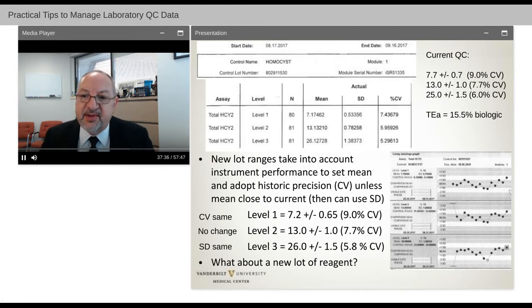the new ranges. So we set our level one, where the CV is the same, 7.2 plus or minus 0.65. This is 9%, and that's still 9% CV, but the SD has changed a little bit down from 0.7 because the mean shifted. Level 2 QC didn't shift at all, means the same, so we keep the SD the same and the CV, 7.7%. And level 3, 26.12, is very close to 25. We kept the standard deviation the same, which narrows our CV just a little bit.